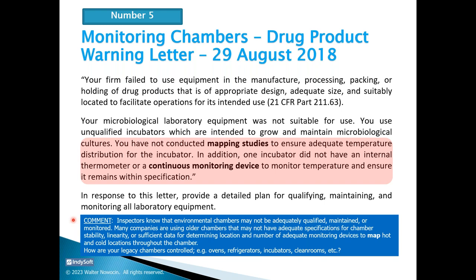Older, my experience is that the older chambers, let's say older than 10 years, do not have adequate specifications, documented specifications for chamber stability, linearity, or sufficient data for determining location and number of adequate monitoring devices to map hot and cold locations throughout the chamber.